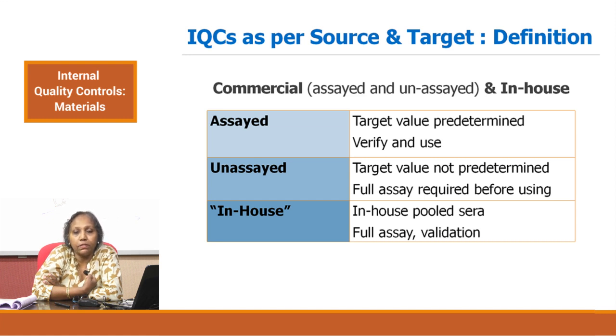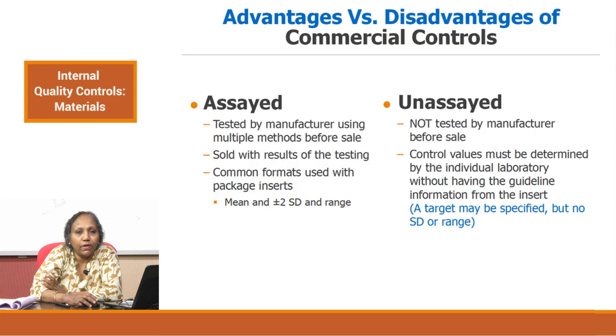Assayed means the target value is predetermined and you only have to verify and use it. Whereas in the case of unassayed controls, target values are not predetermined and a full assay is required before you use it. Let us look at the advantages and disadvantages of commercial controls which are assayed and unassayed in detail.